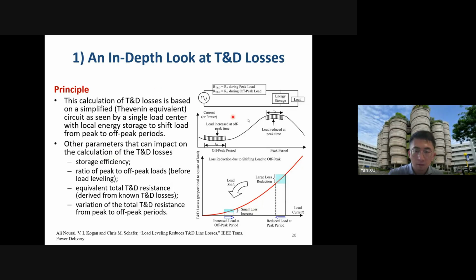This is a general working principle, but we also need to consider other parameters, including the efficiency of the energy storage, because when it charges and discharges it loses energy by itself. As we introduced yesterday, energy storage efficiency varies by technology - lithium batteries may have 95% efficiency, but others may not be as good, especially compressed air ESS.